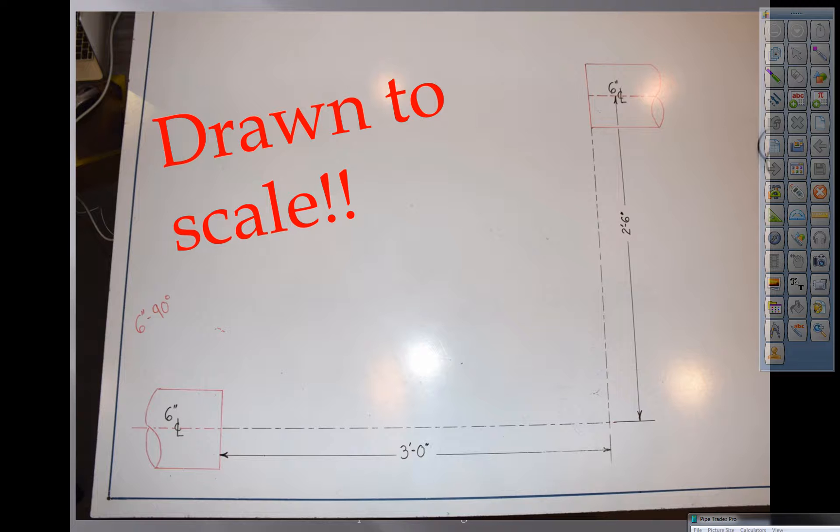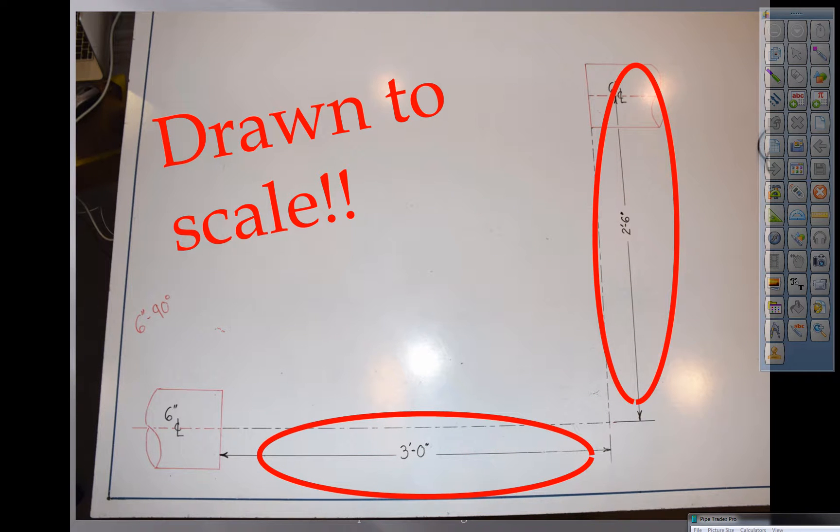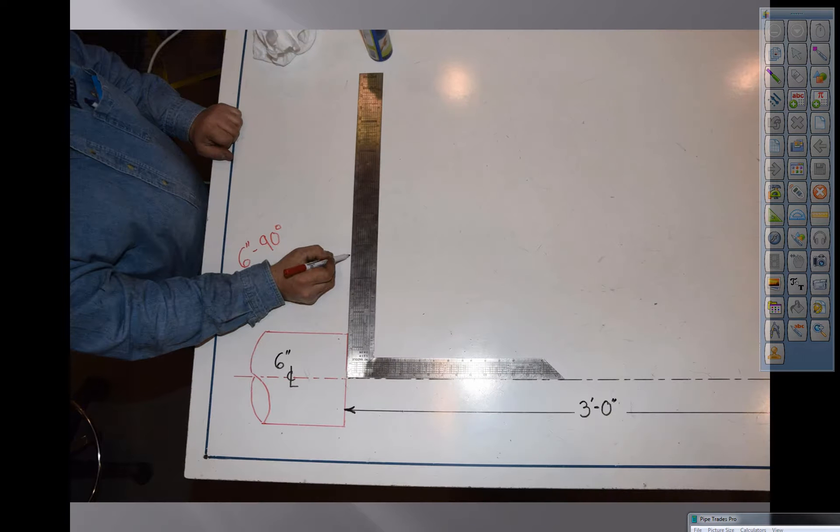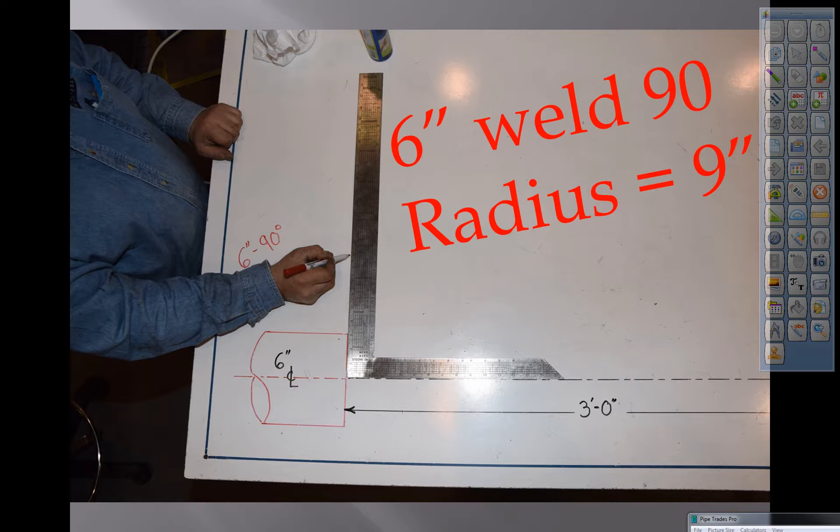So we're dealing with six inch pipe. We have two foot six up and down, elevation change, and we have three foot in a left to right fashion. Now we're dealing with six inch weld fittings. We're dealing with long radius 90s. A six inch long radius 90 equals nine inches, and that's a given.